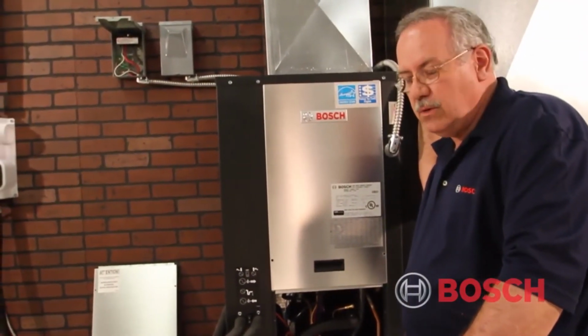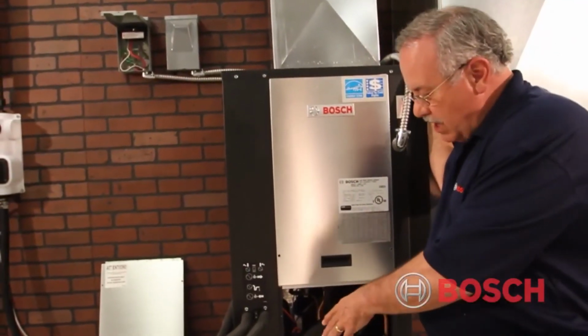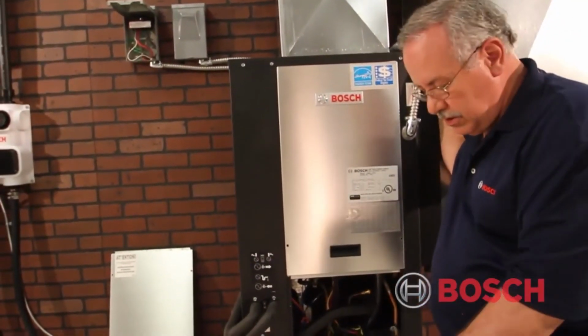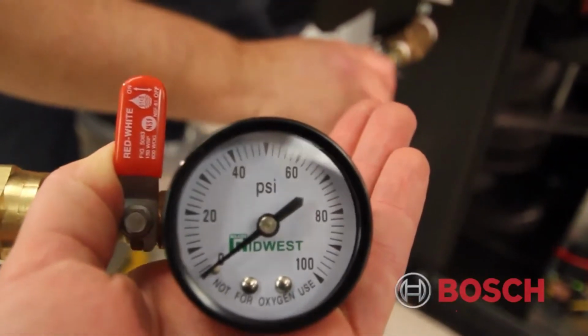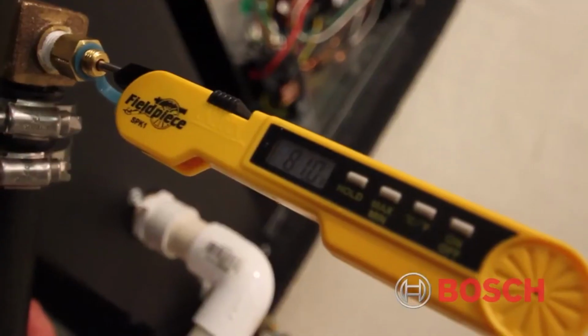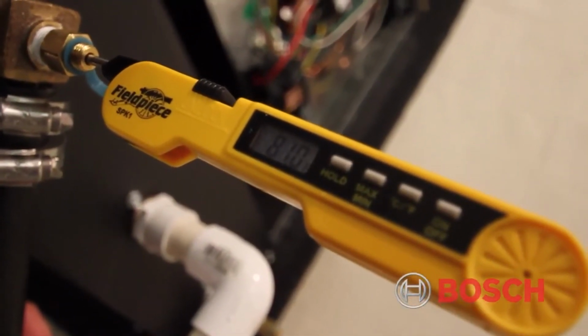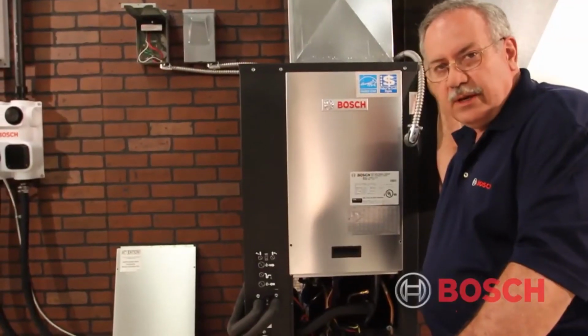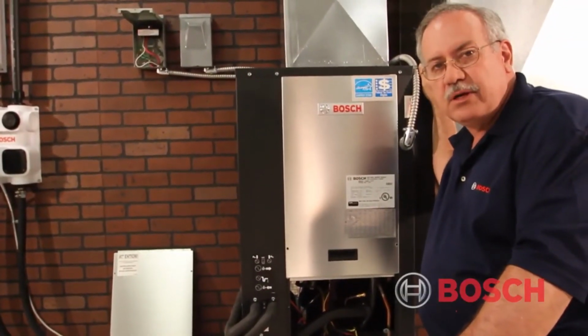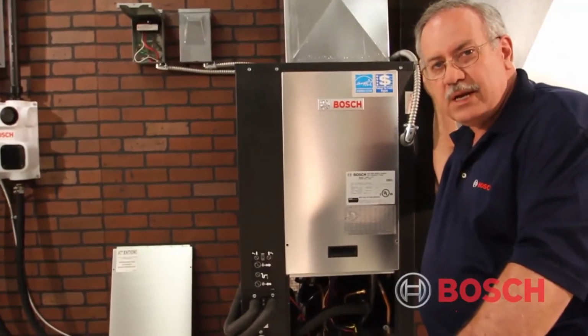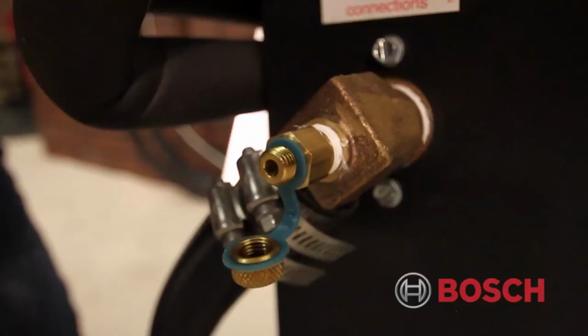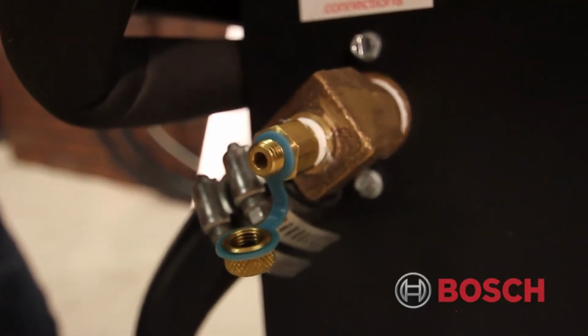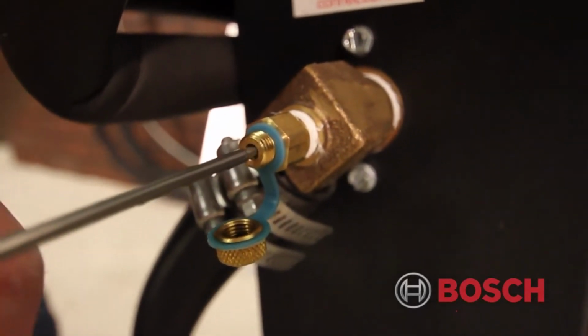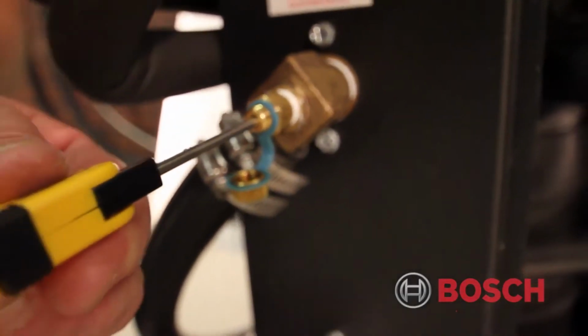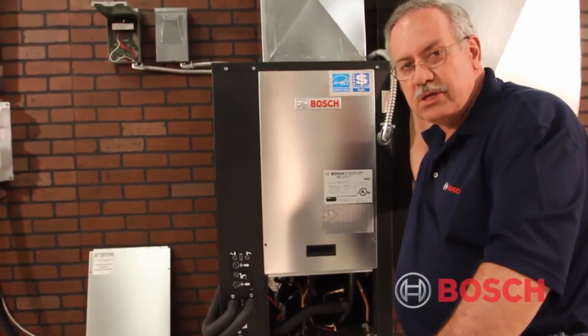So the process that we'll do is I will use available tools, a pressure gauge as well as a knife blade, some people call it that, thermometer, typically digital, and I'm going to go to the pressure temperature ports, commonly referred to as PT or Pete's plugs ports, that are on the entering and leaving side of the coaxial heat exchanger inside the machine. They're on the outside of it, but it's connected to the coaxial in the machine.